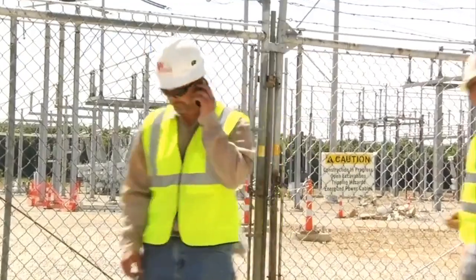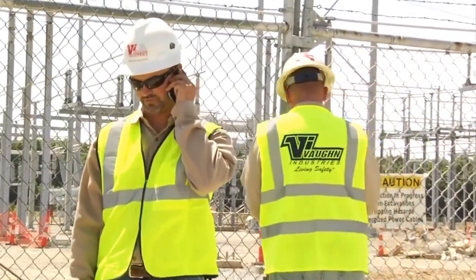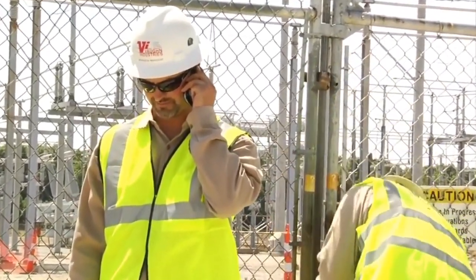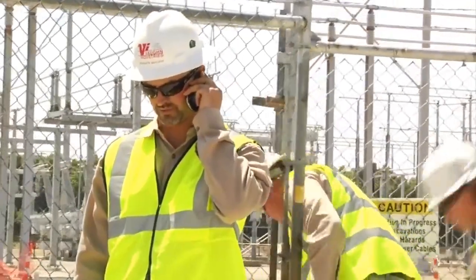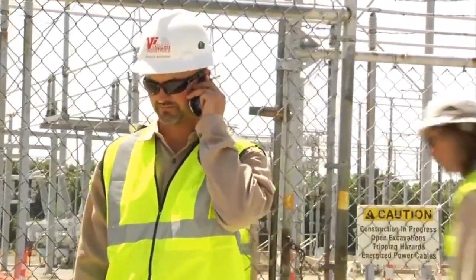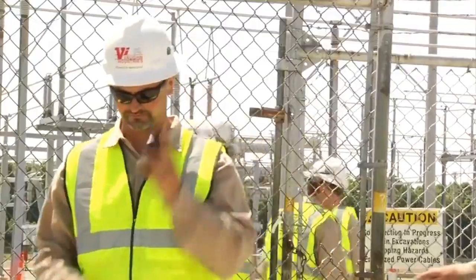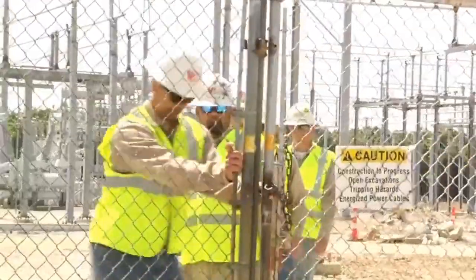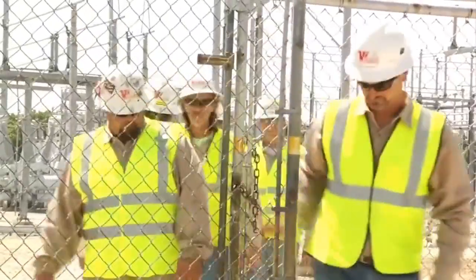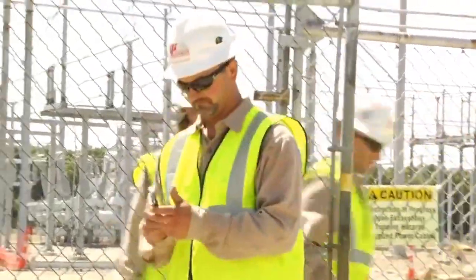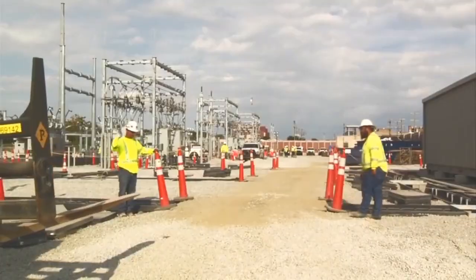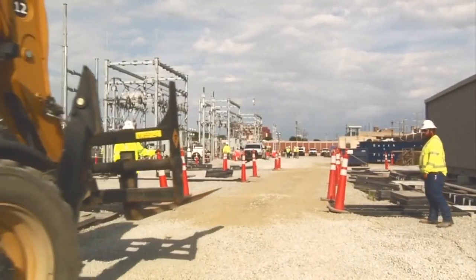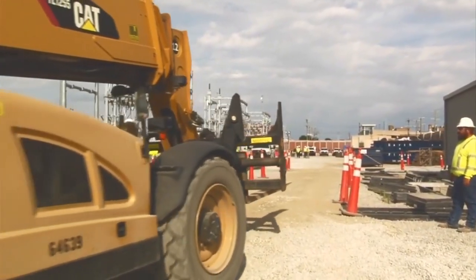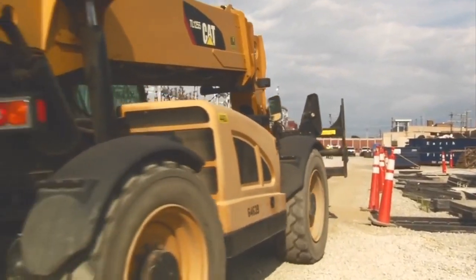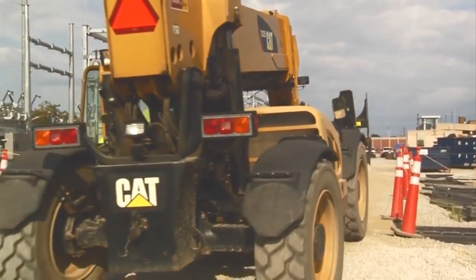When working in a substation or switchyard, the contractor shall keep all gates closed and locked at all times, unless under direct observation by an attendant. Upon entry or exit of a substation, the contractor shall notify the appropriate dispatch authority. If the supervisor leaves the station, all affected personnel shall also leave the site. The contractor shall define work areas and drive paths within the substation or switchyard with barricades to delineate safe distances to structures, equipment, and fixed objects.